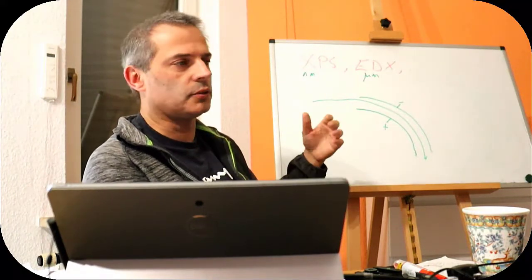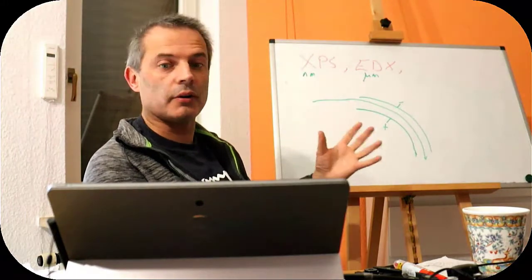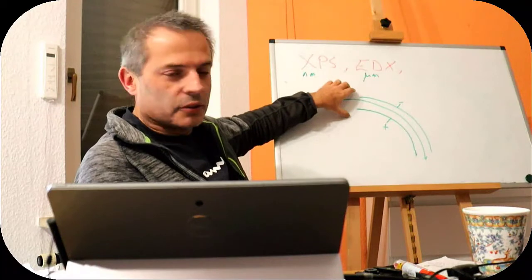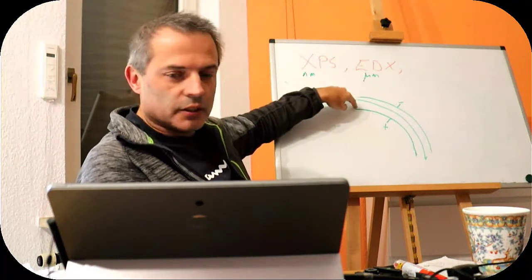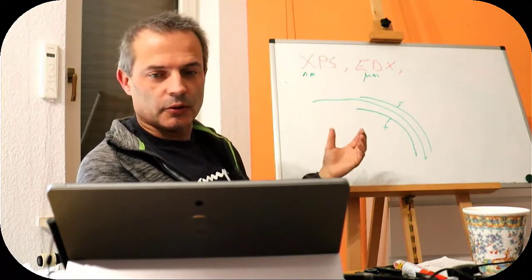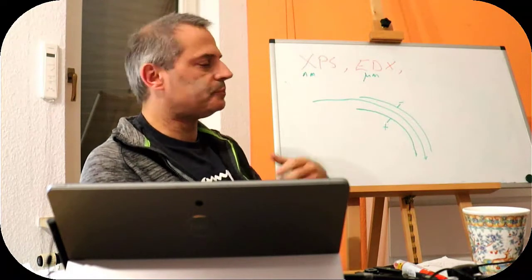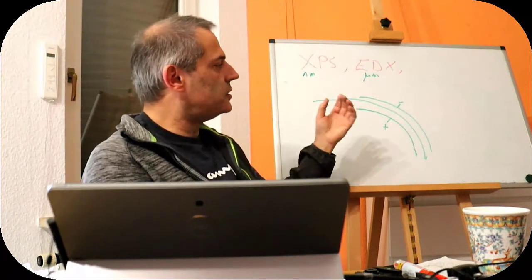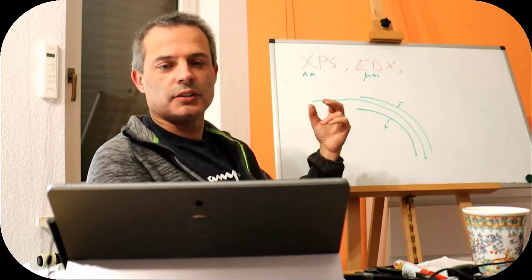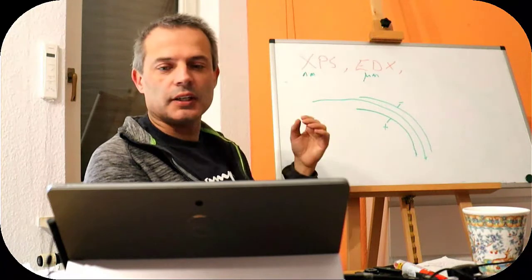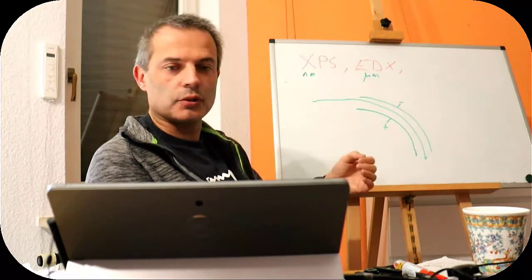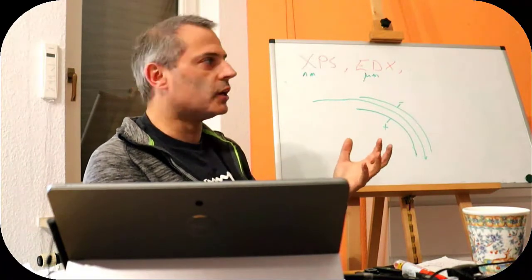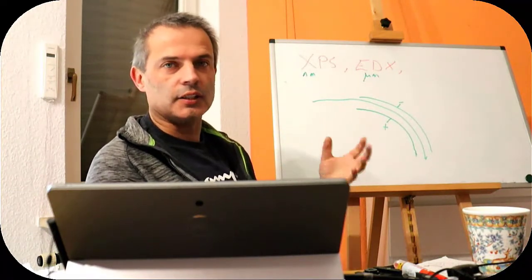This is one way to do it. It's not the only way, but it's one way to do it, and it's comparatively easy to do. The optics on the front end to get the electrons to go into the correct orientation, and the optics on the other end, and counting them is obviously not so easy, but this is the bit that impacts the user, because the user in this case will have to wait for longer because we're measuring one wavelength at a time compared to if we were measuring them all at the same time, but practically it's easier and cheaper to do it this way.